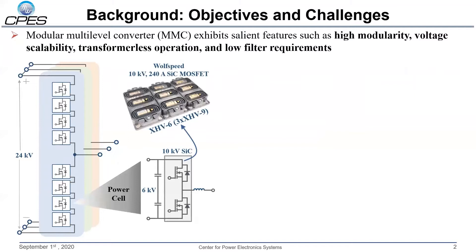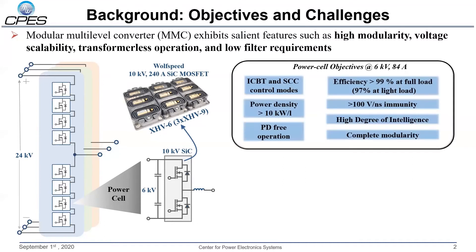MMC's fundamental piece is the power cell. If the kernel part is a silicon carbide MOSFET, the design is capable of achieving high efficiency and power density. Power cell objectives are capability for ICBT converter and switching cycle control. These enable extreme reduction in passive component size, power density of 10 kW per liter, partial discharge-free operation, 99% efficiency, and high common-mode transient immunity.